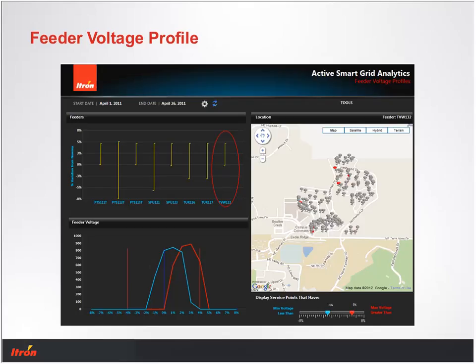For the selected feeder up top, the lower left-hand quadrant shows the distribution of your highest and lowest voltages for every service point - kind of a histogram, but done as a line graph since an overlapping histogram is hard to look at. That's your distribution of voltage along each feeder.